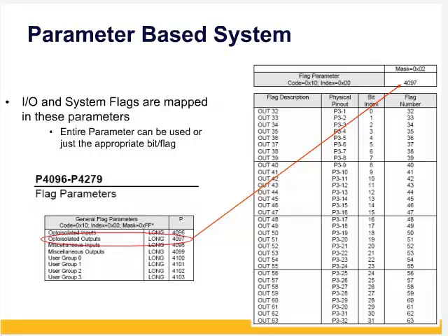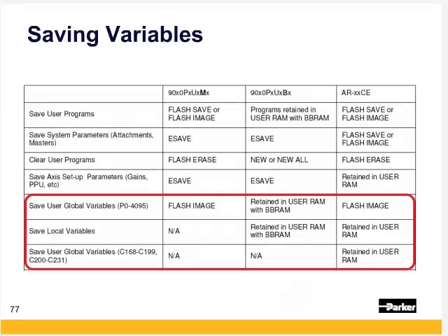Note that for system flags, these map to a long parameter, such as outputs 32 through 63 mapped to parameter 4097, allowing users to set more bits with an integer in one line of code instead of 32 lines of code for 32 bits.